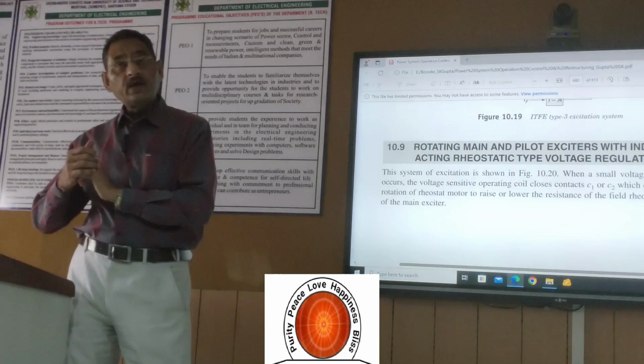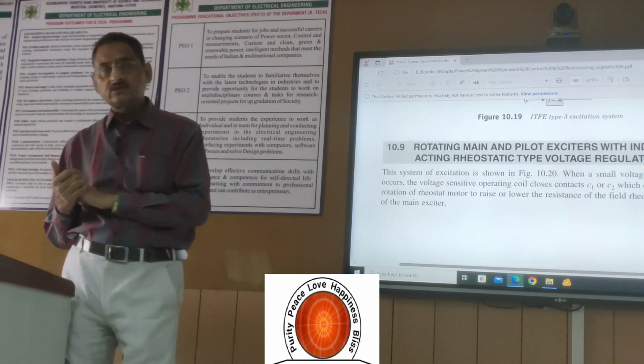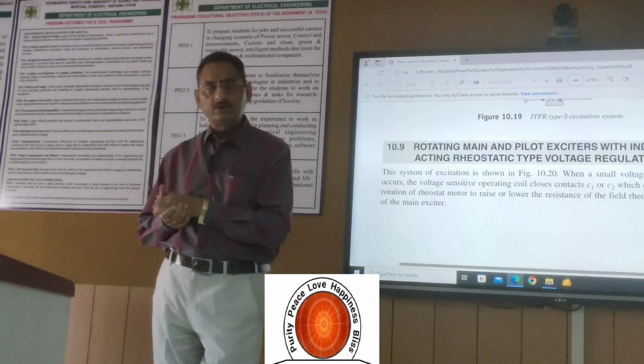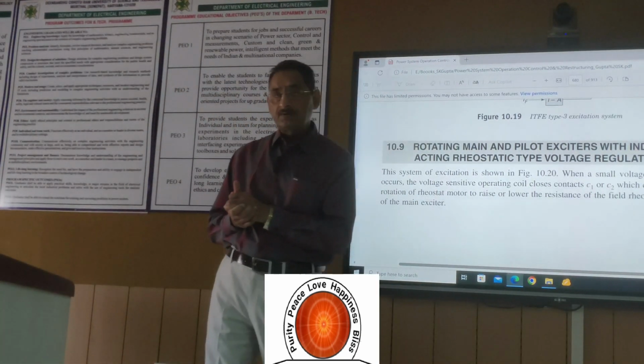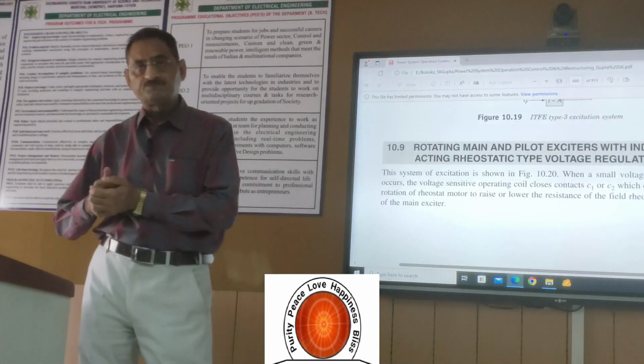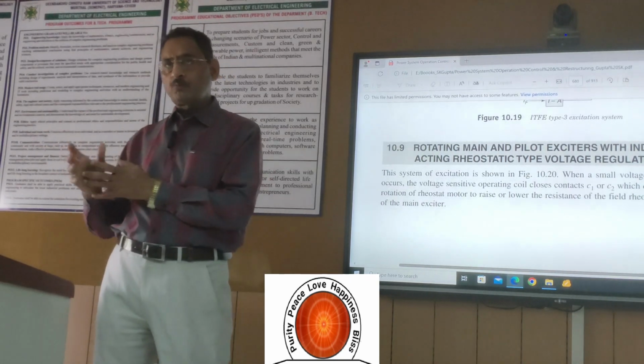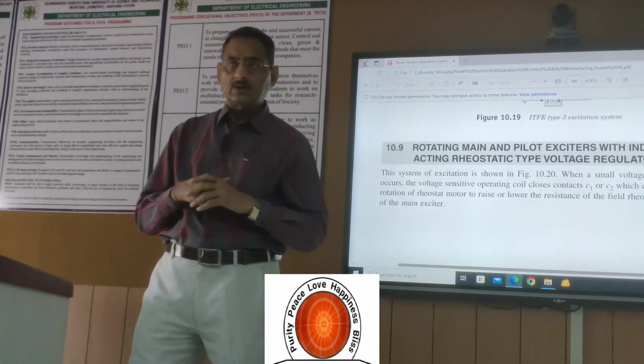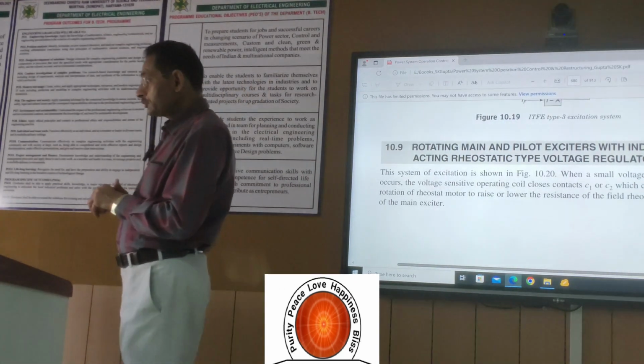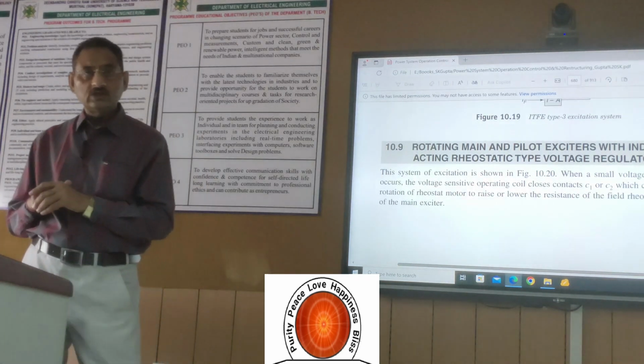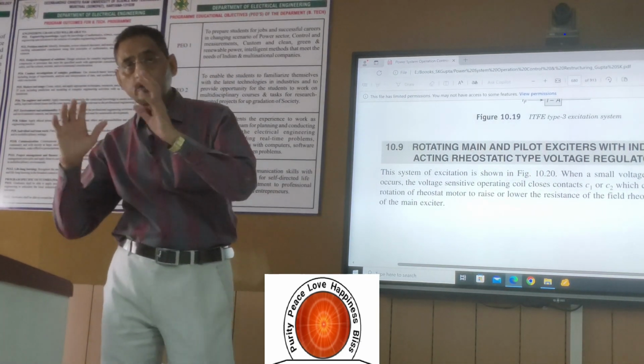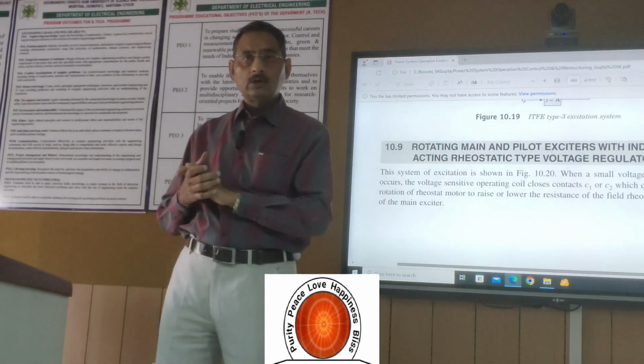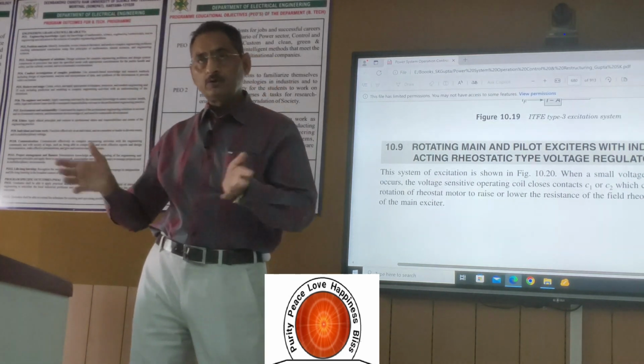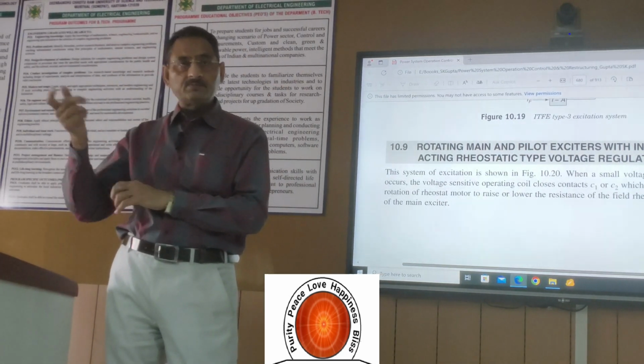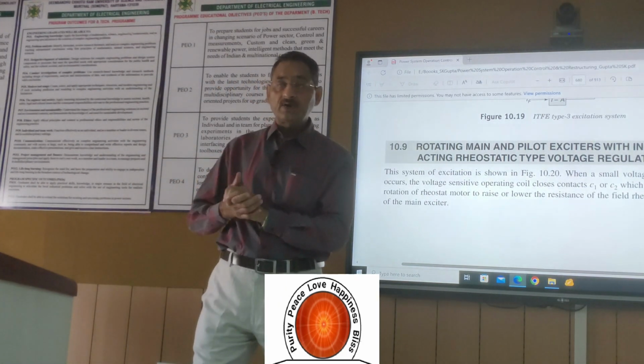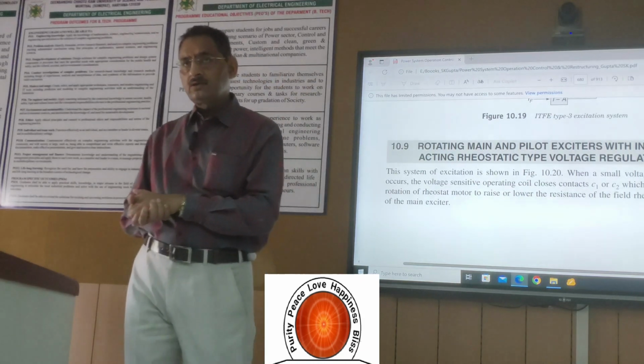See, in the main generator, the power generation is done at a high voltage level. The voltage level may be 11 kV, 13 kV, 20 kV, 25 kV or even 33 kV. Power can be generated at this voltage. If the voltage is high, then for the same amount of power the current is less. But in the case of the exciter, the voltage level is not high. If the voltage level is low, say 1 kV, then for a 100 kW exciter the current will be 100 ampere.